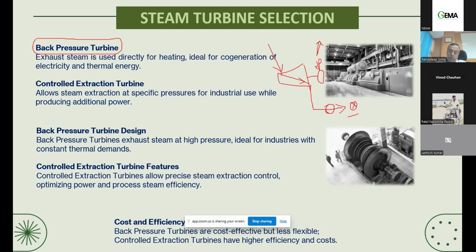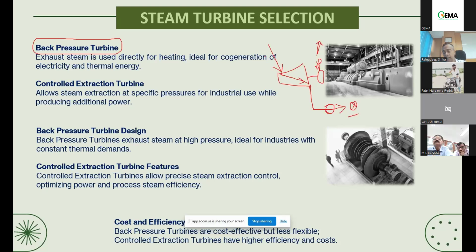Suppose I have a 14 megawatt steam turbine and my steam demand is say 50 or 60 TPH, just for discussion's sake. I decide, okay, I need some more margin, so I will go for a 16 megawatt unit, but my steam requirement I am not increasing, I maintain it again at 60 TPH only. So tomorrow, when my demand actually becomes 14 megawatt, I will not get 60 TPH from the turbine, because if my turbine is running at a lower load, I have to provide lesser steam to the main steam, and therefore the quantity of steam coming out of the turbine will also be less. It is almost a straight line relationship.